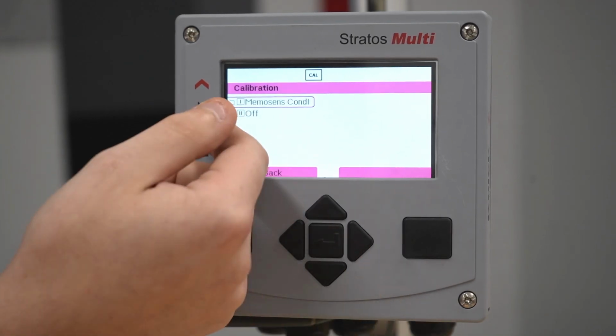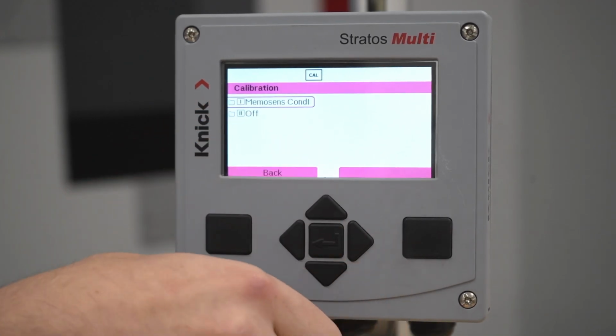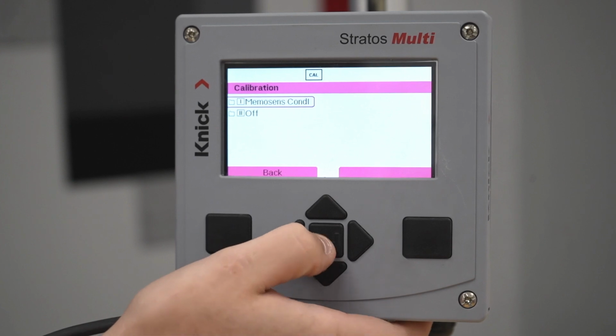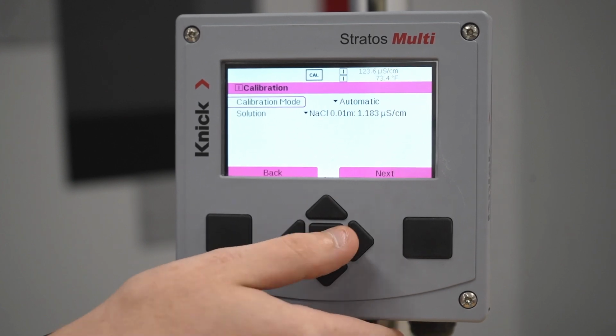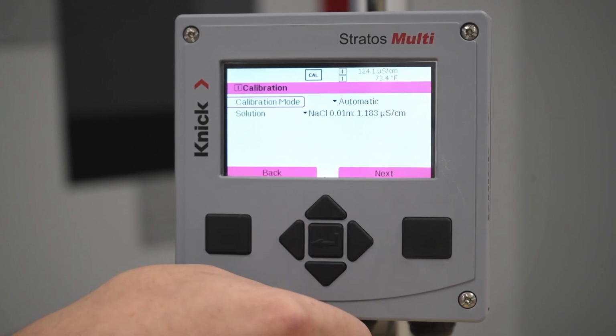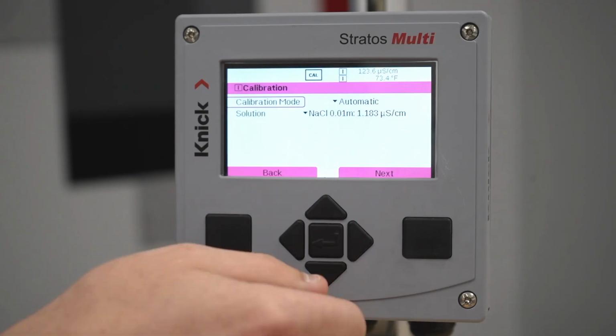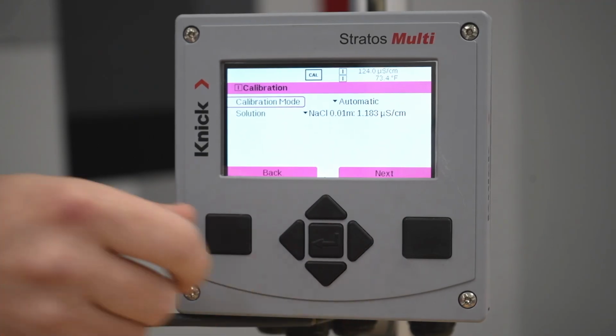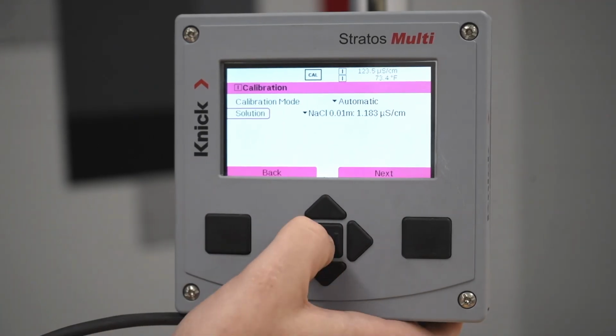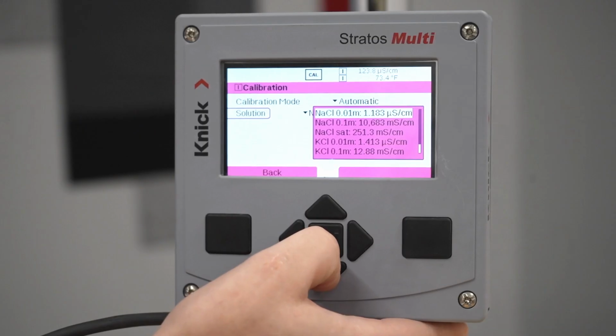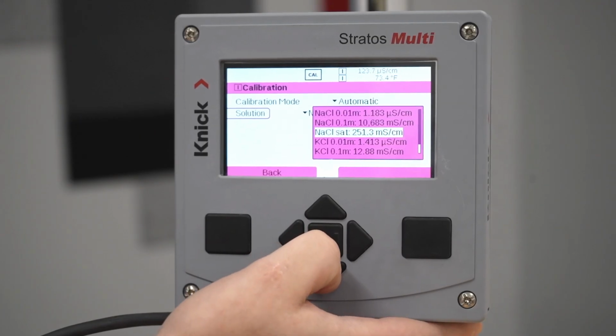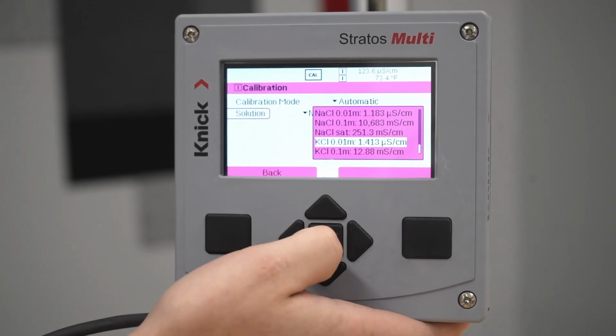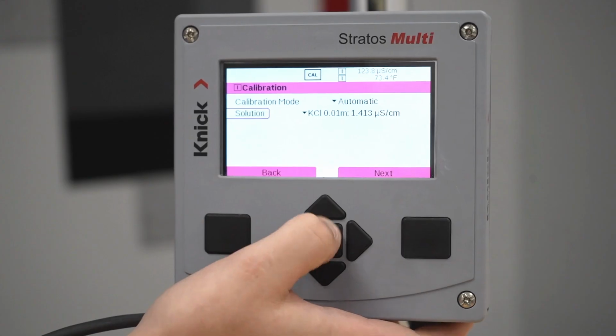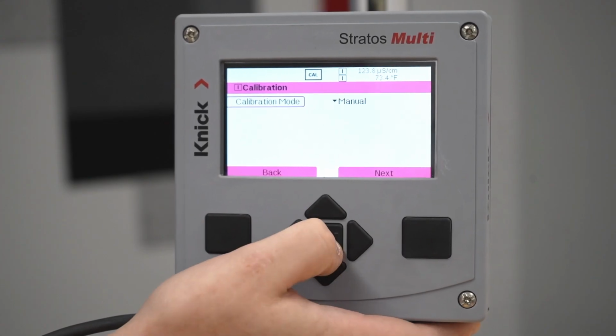And then this might be on your second channel if this is run through an input card, but you're going to select Memosens CondI for inductive cond. And then once you get into your calibration screen, you get a couple different options. If you would like to do an automatic calibration, we can do that, but you would need to ensure that your conductivity buffer selected matches the solution set for this calibration. The one I'm using is not in here, so I will be using a manual calibration.